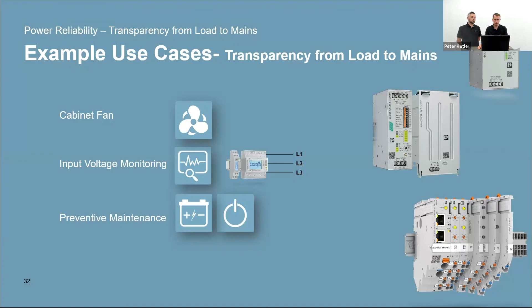...preventive maintenance. So if you have a business model where you maintain your customer's application, or want to reduce costs in your own application, we recommend using products with lifetime monitoring, like the Quint Power system, CAPAROC, and Quint IQ. Here you can know the remaining battery lifetime, and uniquely, the Quint IO-Link devices we showed in 20 and 40 amp are also capable of monitoring their lifetime. This way you don't replace the power supplies and batteries too early, and you always have the right time, not too late, so you don't lose power reliability.